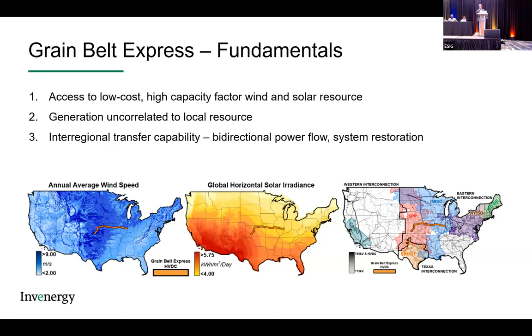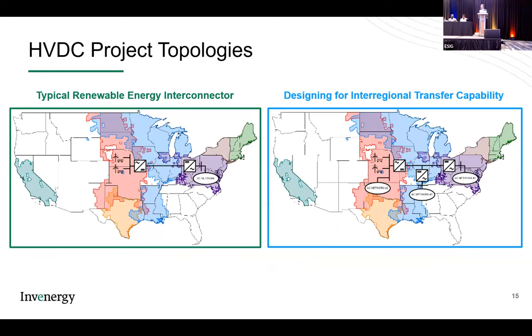So looking at the project, at the root of it, you're bringing renewables to areas that don't have access to renewables. We talked about MISO earlier. They have pretty high penetration of renewables. Why would we add a terminal in MISO? And it's going back to the root of it. There's opportunity there for this interregional system backbone. There's opportunity to get generation that's not correlated to the local, and again, higher capacity factors.